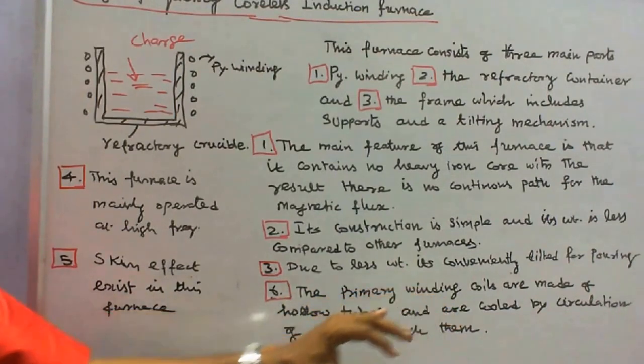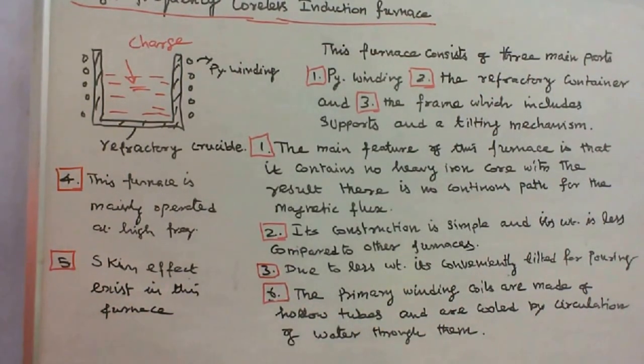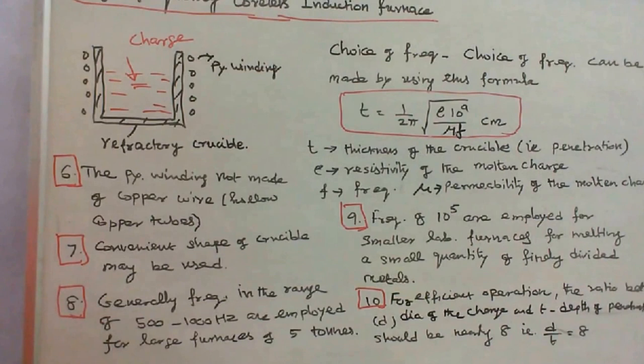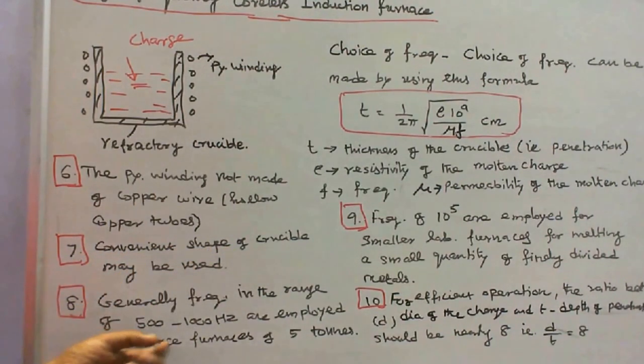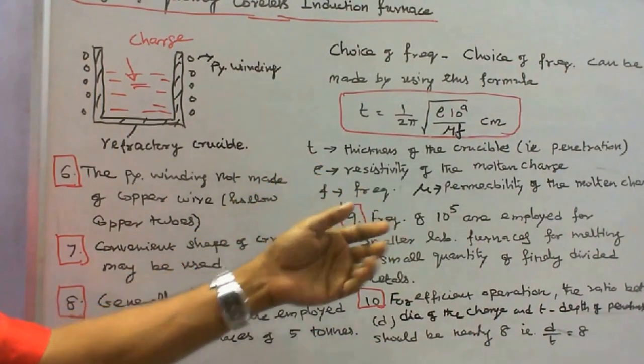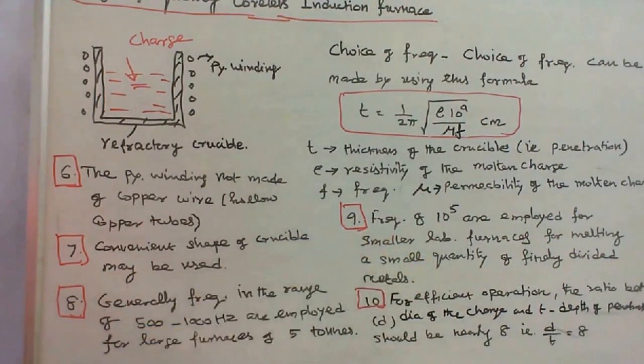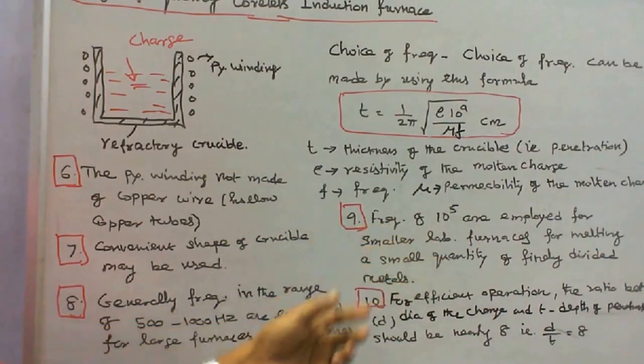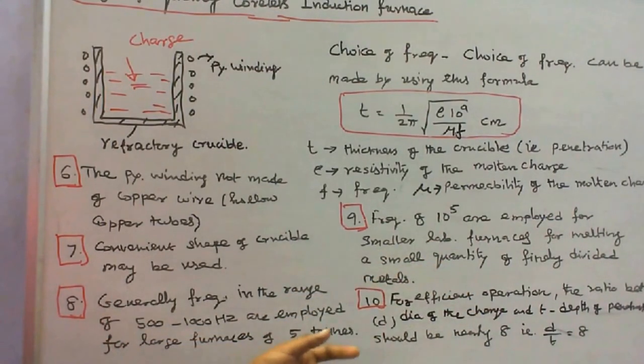The primary winding coils are made up of hollow tubes and are cooled by circulation of water through them. Hollow copper tubes are used instead of copper wire. Any convenient shape of crucible may be used. Generally, frequencies in the range of 500 to 1000 Hz are employed. For larger furnaces of 5 tons, lower frequencies are used, while higher frequencies of around 10^5 Hz are employed for smaller laboratory furnaces for melting small quantities of finely divided metals. For efficient operation, the ratio D/T, where D is the diameter of the charge and T is the depth of penetration, should be nearly 8.